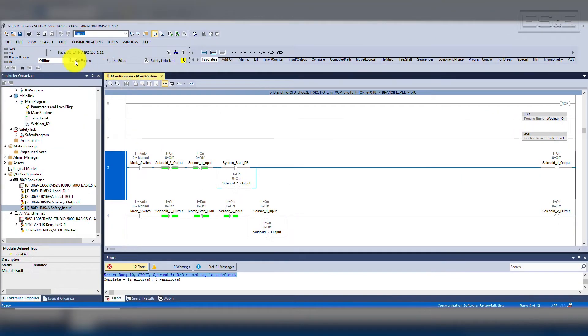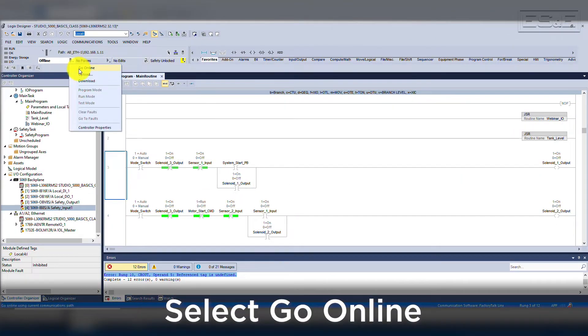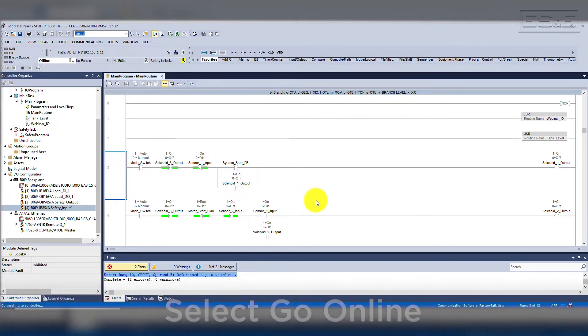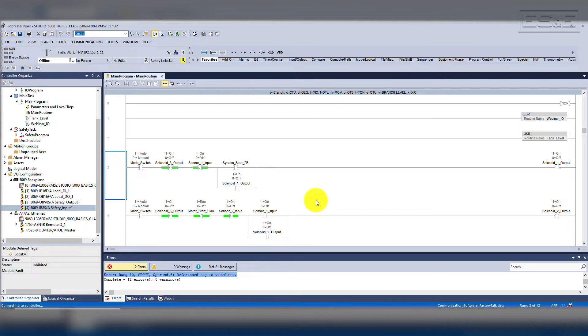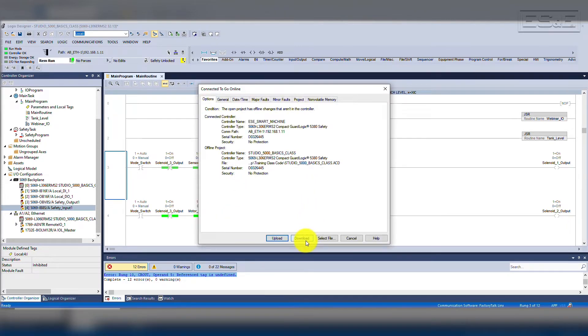Now the configuration is good, so we can select our dropdown and go online. When you select Go Online, it will automatically check for configuration differences between the offline project file and the online controller. If they are not the same, a pop-up window will appear asking if you want to upload, download, or cancel going online. If you know the changes that were made and need to overwrite the controller, press Download. If not, it is always best practice to select Upload.